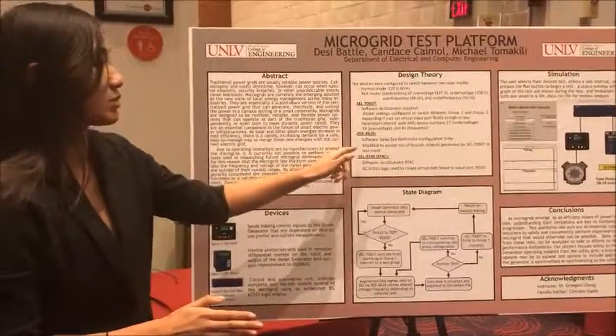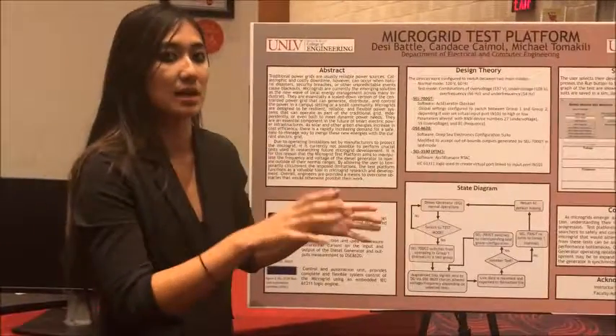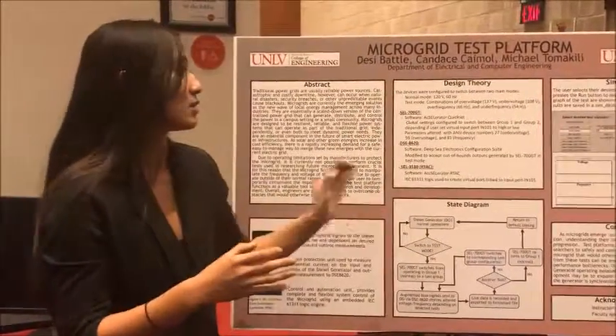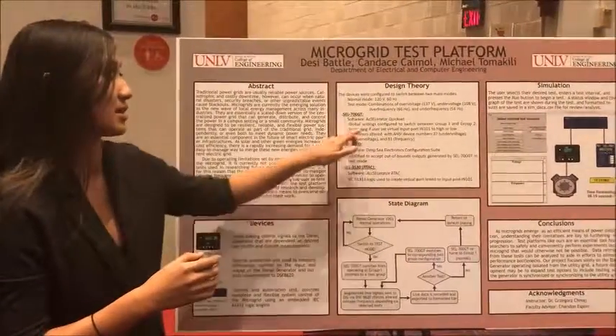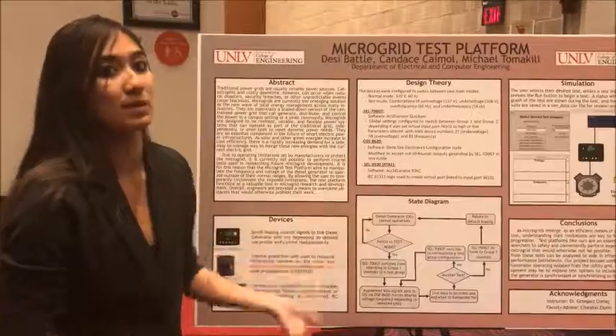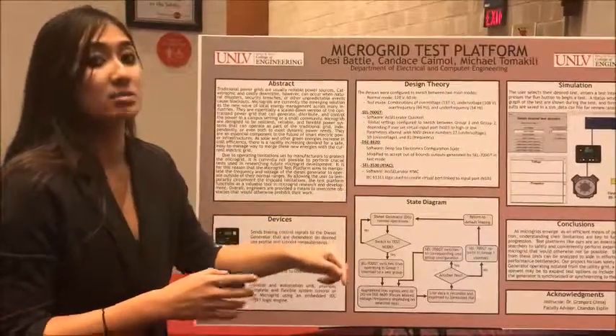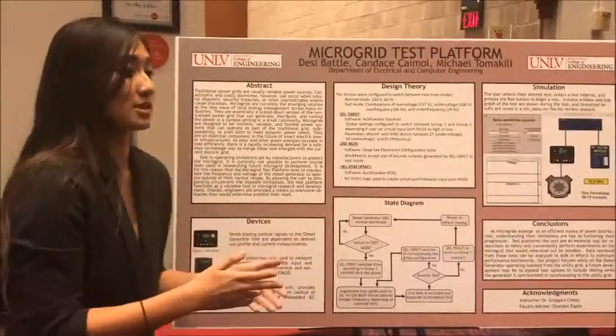For the DSE8620, which sends biasing signals to the generator, we had to modify it to accept the out-of-bounds outputs from the SEL700GT. This was done using the Deep Sea Electronics Configuration Suite, manipulated in a similar manner to the SEL700GT. For the SEL3530 RTAC, which is essentially the brain of the entire system, the software used was Accelerator RTAC. This takes IEC logic and was used to create the virtual port for the user to toggle between test groups.